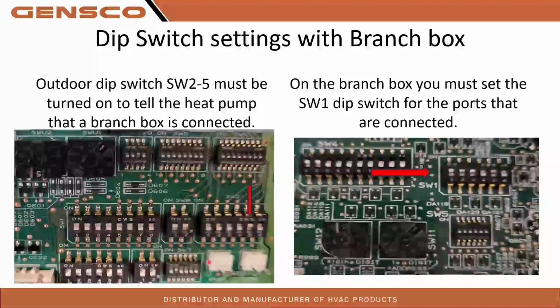SW2-5, if you're using a branch box, that will need to be turned on to tell it that there's a branch box. Again, the system will operate with a branch box with that turned off, but it changes how it meters flow to your indoor head, so your performance may suffer a bit. So that's something we usually look for when we're doing our phone support and site visits, to make sure that switch is on if they have a branch box.